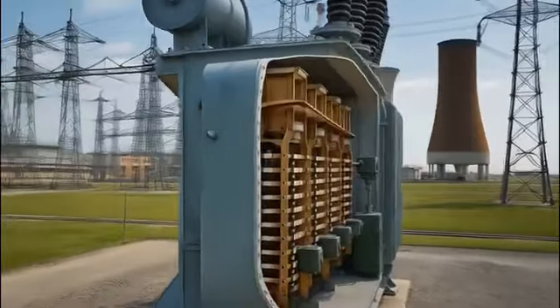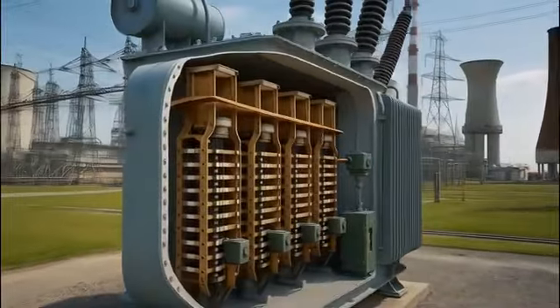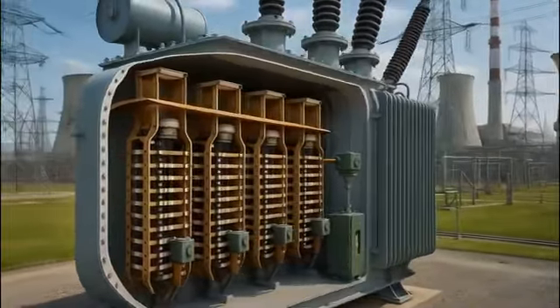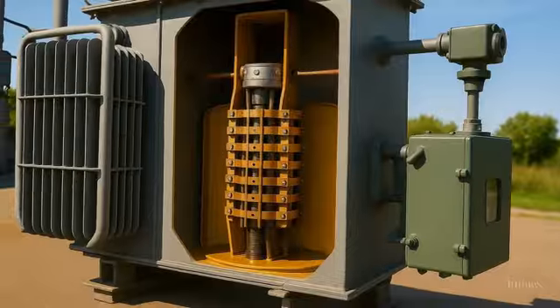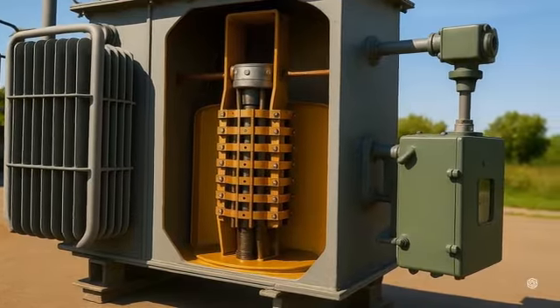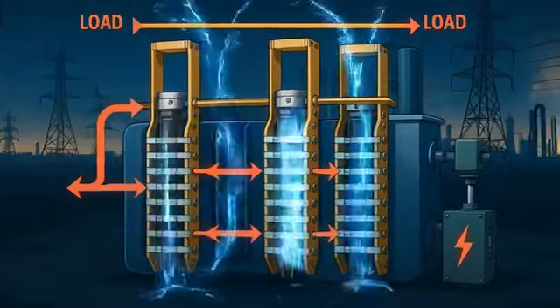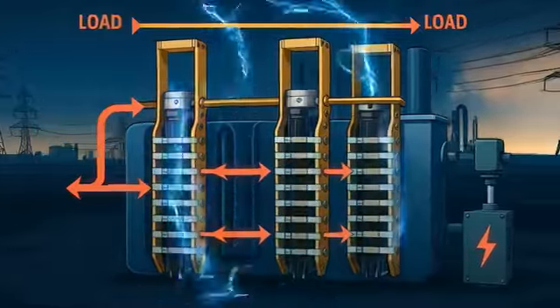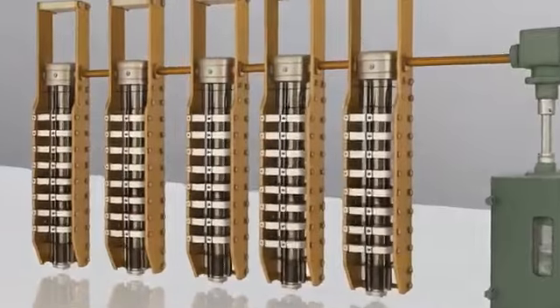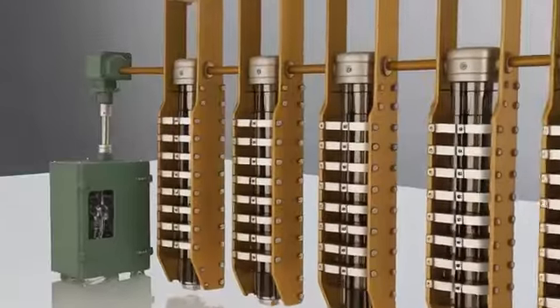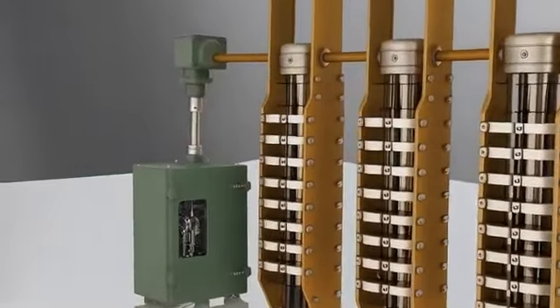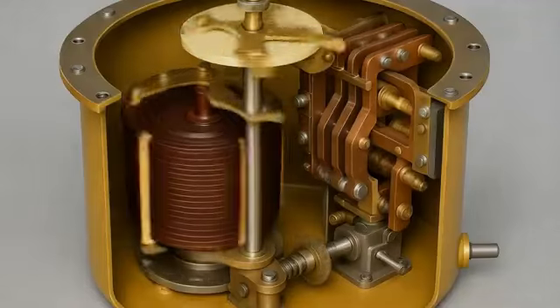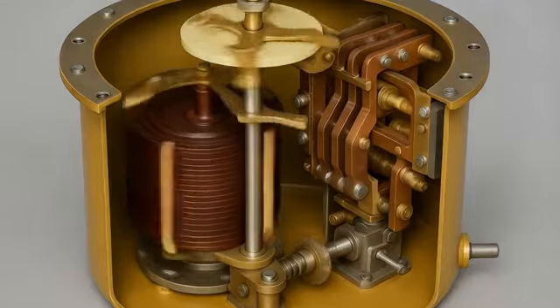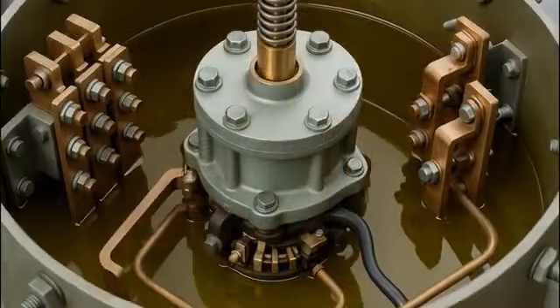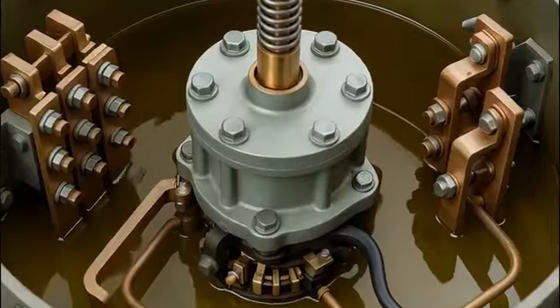An onload tap changer, OLTC, shall mean an onload voltage regulator. As the term implies, the main purpose of this device in transformers is to regulate the voltage under different loads. Since an onload tap changer constitutes the only component of a transformer that has moving members and contains more than 300 individual parts, its servicing and maintenance require routine inspections, as well as involvement of certified professionals.